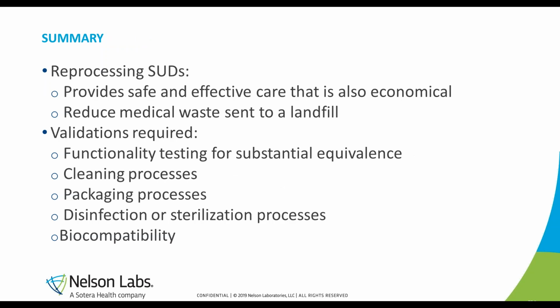In summary, the motivating factor driving the demand for third-party reprocessing of single-use devices is a desire to provide safe and effective care that is also economical, ultimately benefiting the patient. Furthermore, the amount of medical waste sent to landfill can be reduced significantly through reprocessing activities. Paramount to these efforts is validated function testing, cleaning processes, and disinfection or sterilization processes. Establishing substantial equivalence of the reprocessed single-use device to the original device design status demonstrates the finished device is safe and effective for use.